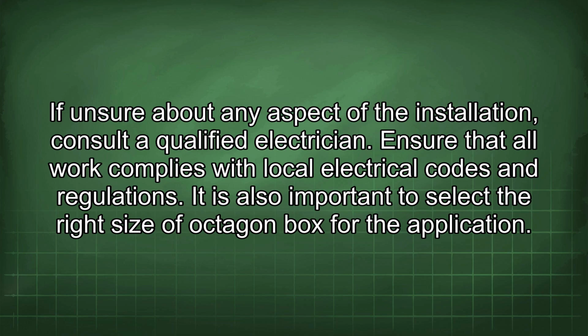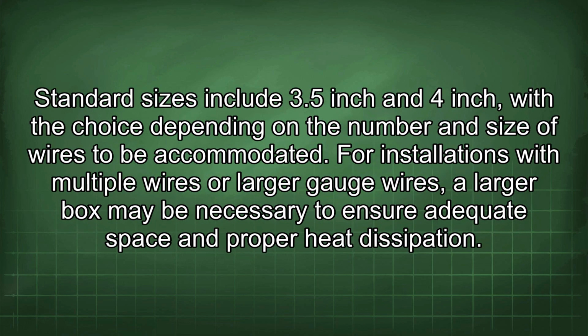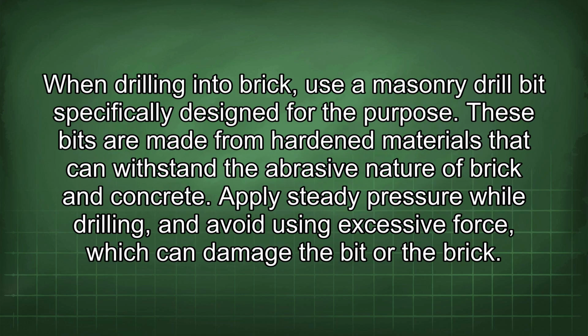It is also important to select the right size of octagon box for the application. Standard sizes include 3.5-inch and 4-inch, with the choice depending on the number and size of wires to be accommodated. For installations with multiple wires or larger gauge wires, a larger box may be necessary to ensure adequate space and proper heat dissipation. When drilling into brick, use a masonry drill bit specifically designed for the purpose.